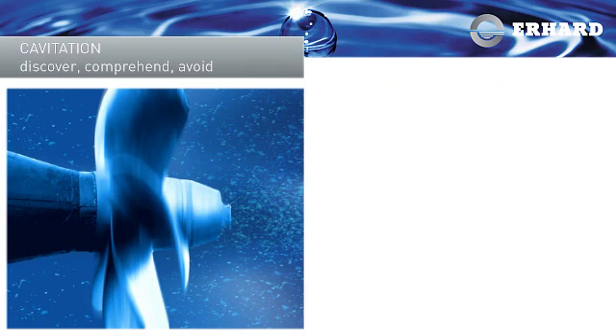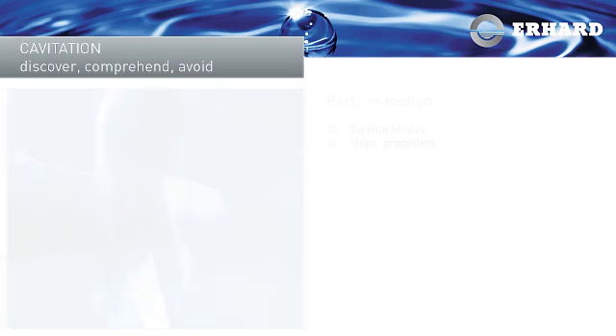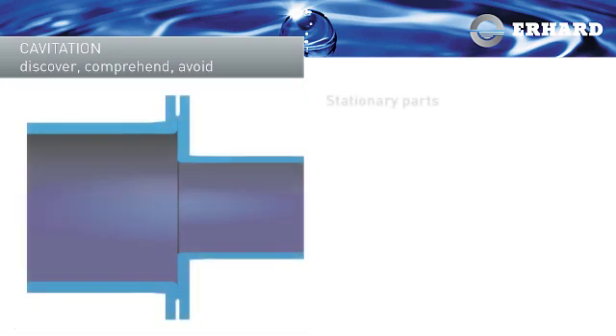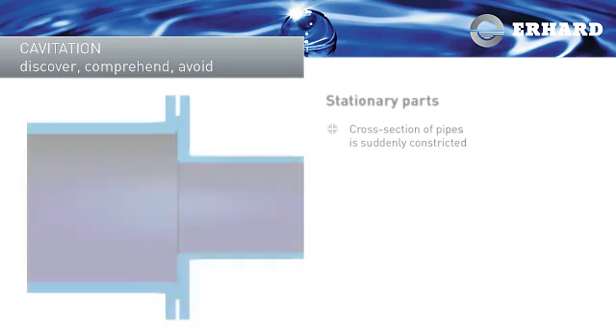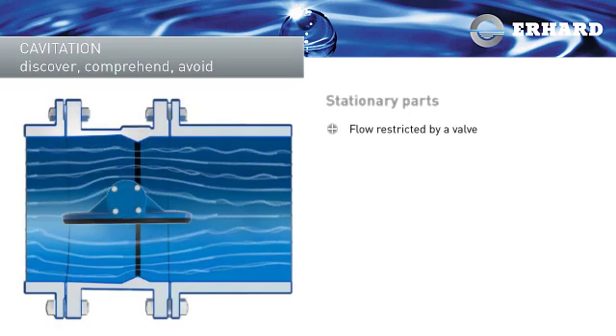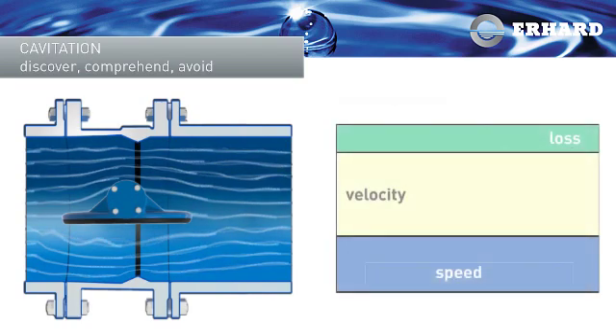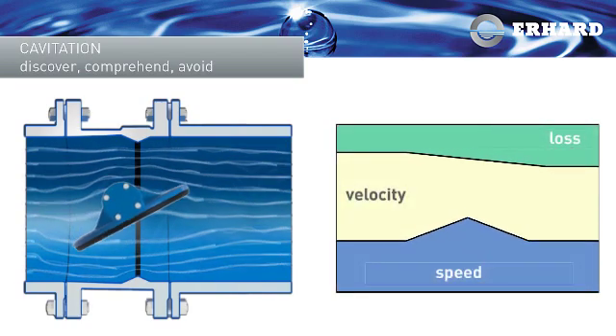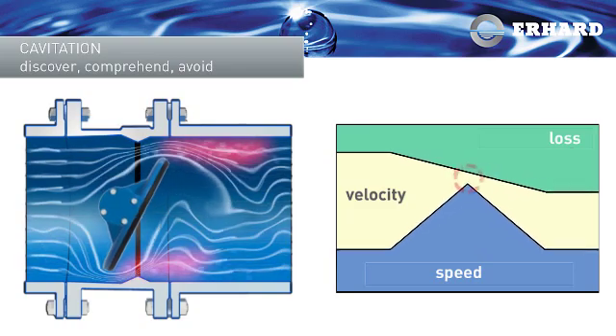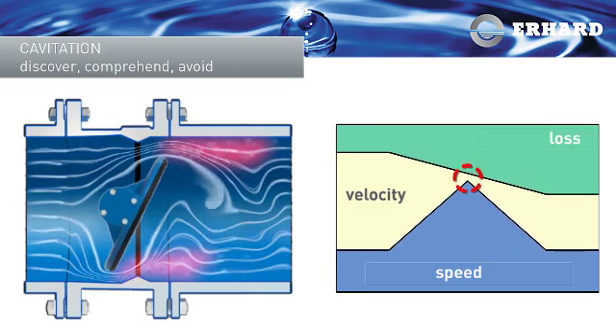Cavitation, for example, can occur in turbine blades or ship's propellers, but stationary parts are also affected by it — for example, if the cross-section of pipes is suddenly constricted or if the flow is restricted by a valve. Strong velocity conversions are generally the cause of the pressure changes which initiate cavitation.